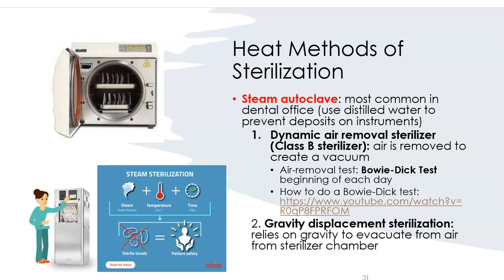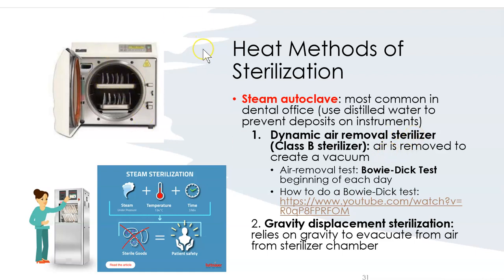To sterilize, we use autoclaves, typically with distilled water rather than tap water to prevent deposits on instruments. The two main types are: the Class B sterilizer (dynamic air removal), where air is removed through a vacuum — this requires a Bowie-Dick test; and the gravity displacement sterilizer, where gravity evacuates the air using high steam temperature for a set time to achieve sterility.